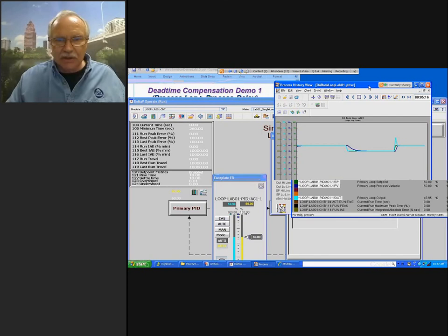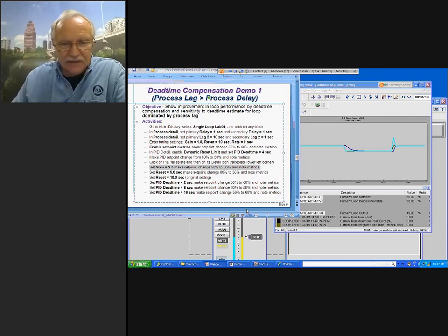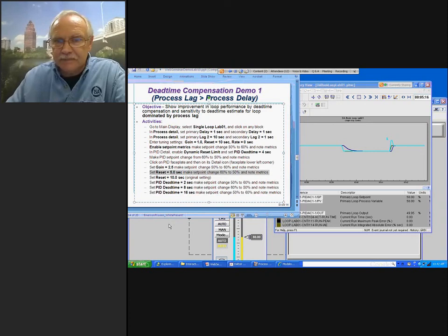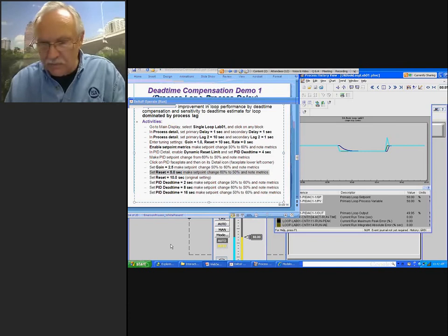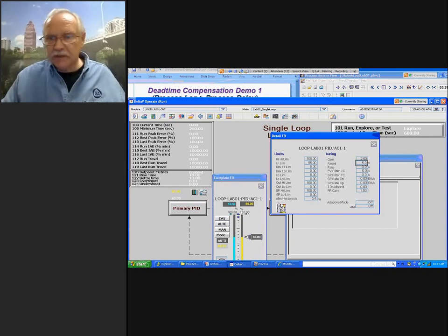Let's see though, hey, can we reduce the reset time? Because as noted for dead time dominant loops, that is a possibility. So we're going to try what's going to happen here by cutting the reset time in half. And we're going to make another set point change. And we'll see what happens.